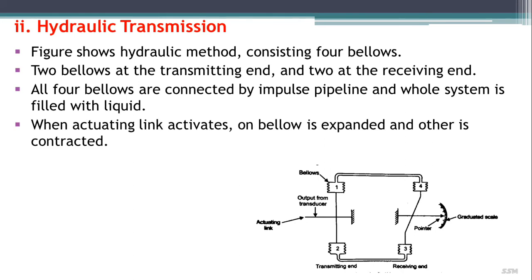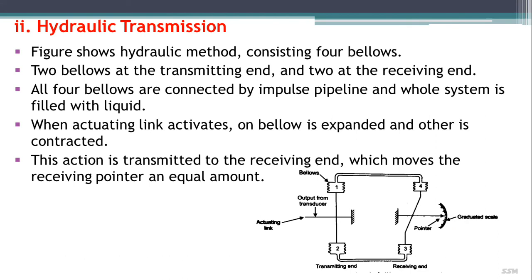When the actuating link on the transmitting end is operated by the measurement, one bellows expands and another contracts. If the output from the transducer actuates bellow one, it expands and bellow two contracts, so that the impulse effect is imposed on bellows three and four. The deflection of the pointer can be observed in the respective direction — the action is transmitted to the receiving end, moving the receiving pointer by an equal amount. The purpose of using two bellows on either side is to compensate for changes in ambient temperature.